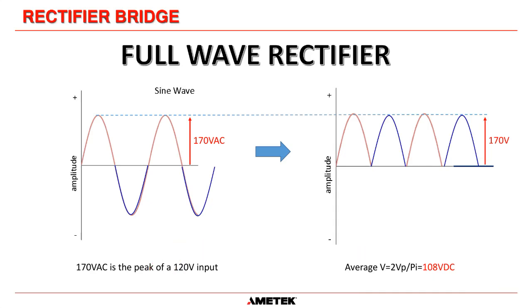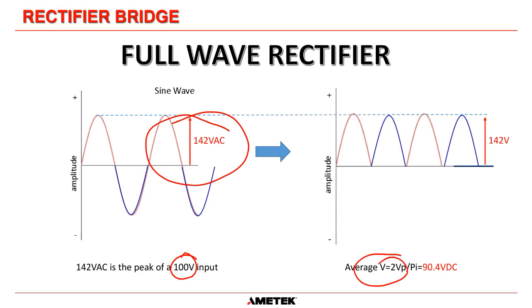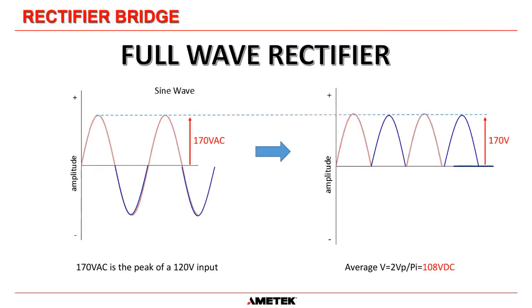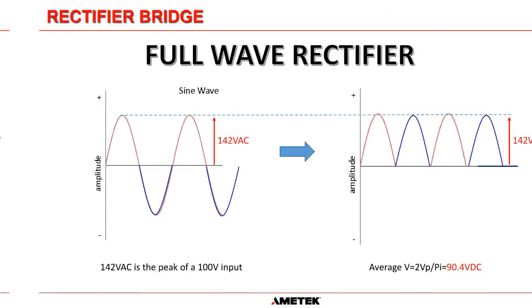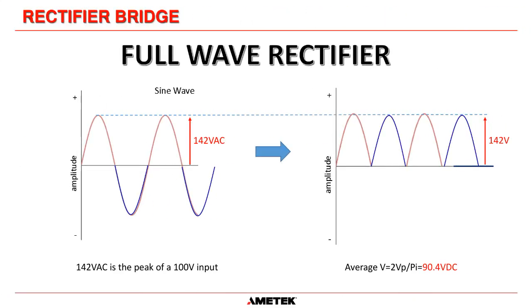But remember, all of our chargers are supplied by grid power, and we do not know what the grid is going to send. We don't know what your transformers in your plant are set at - maybe running slightly high, 500 volts for a 3-phase system, or slightly low, 460 volts. So if your AC went down to 100 volts RMS, the peak is now 142 volts, and the average has gone down to 90.4 volts DC. Previously it was 108 volts, now the average has gone down to 90 volts. We have no control over that - that's what the grid is doing.